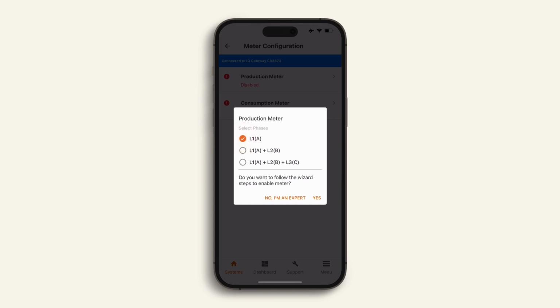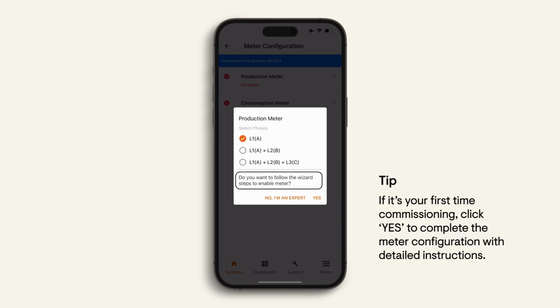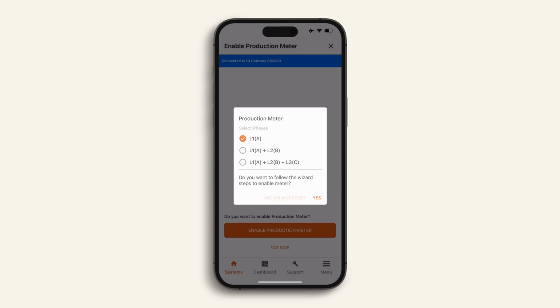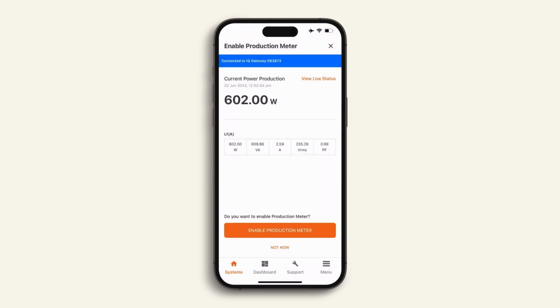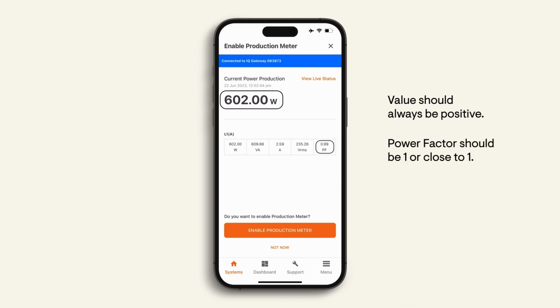If you are new to Enphase commissioning, you can also choose to run through the metering wizard, which will give you a detailed step-by-step check to confirm the CT reading is as you expect. Otherwise, select No, I'm an expert to turn on the CT and view the readings. You're required to enable the internal CT metering of the IQ system controller. Before you press Enable, be sure to confirm the readings look correct. The value should always be positive and the power factor should be 1 or close to 1. If the power factor is very low, for example 0.3, then check your wiring for correct phase connections. It is always good to check this reading.